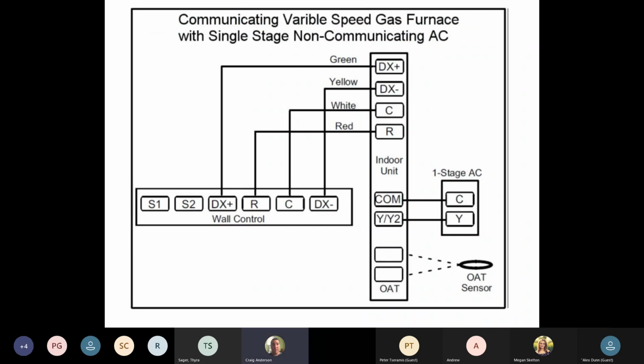So here is where we get to, we have a fully communicating indoor unit because we know we have to if we want a communicating stat. People want to keep their AC outside for now. We'll replace it in a couple years. No problem. We'll just hook it onto our terminal strip downstairs at the furnace. And when we first turn our thermostat on, like I said, it's going to search for an outdoor unit. If it doesn't find one, it's going to ask you if you got one. Answer the questions and move on.